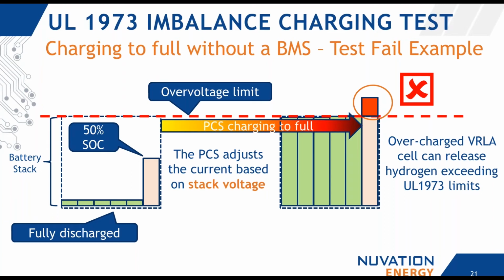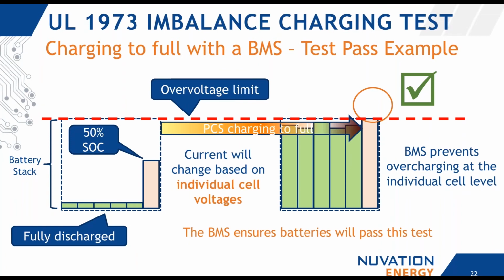The key takeaway here is that without a BMS, the PCS is determining the charge limit based on stack voltage, which is kind of assuming the average of individual cell voltages. And so that can miss the high cell by the time the average reaches the full mark. At that point, that cell can become overcharged and can vent. Since the BMS is monitoring each individual cell, it knows when that cell is reaching full and can avert the charge current. It basically just trips and opens the high current path before any outgassing can occur. So this takes a test that potentially could fail or lead to an undesirable result, and it makes it kind of boring. You know that this test will pass.